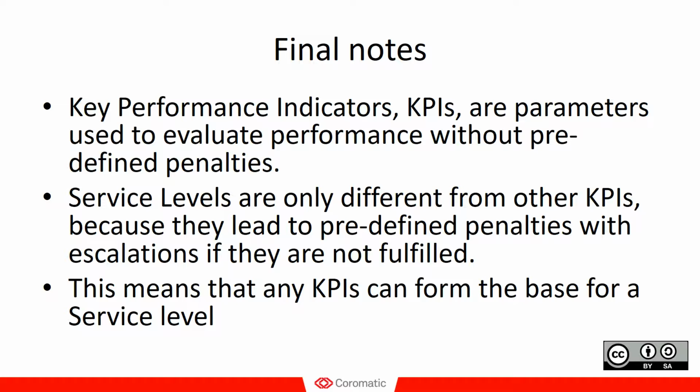You can simply see what is the current PUE and what is maybe the rolling 12 months PUE average and so forth. But if you add to that same KPI and say that the PUE should never be above a certain threshold, and if it is, it will cost a certain amount or it will trigger an escalation event or whatever it is, that turns the same KPI into being a service level.